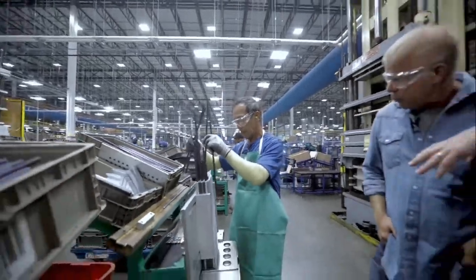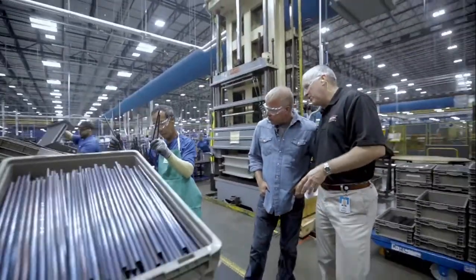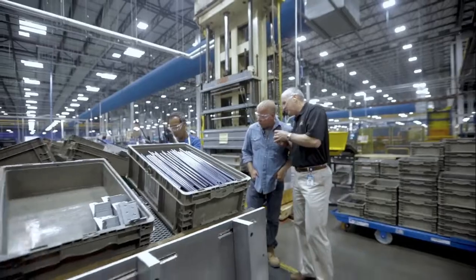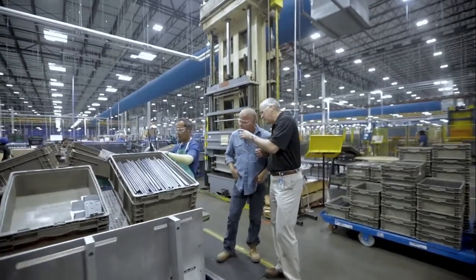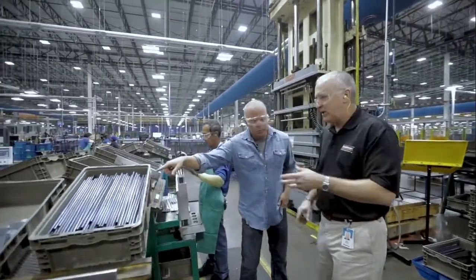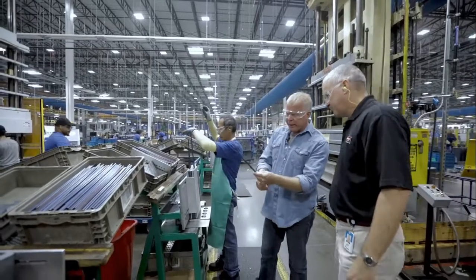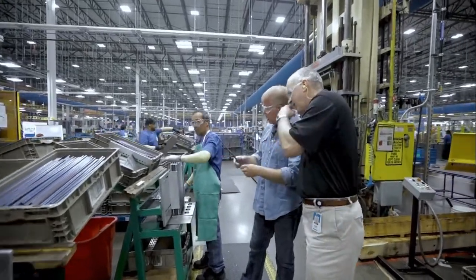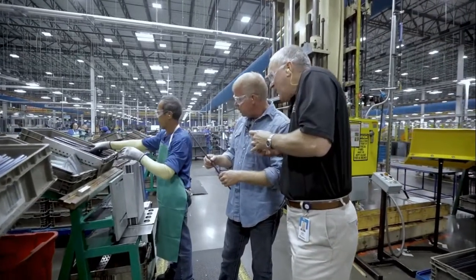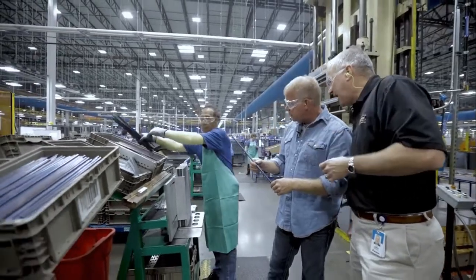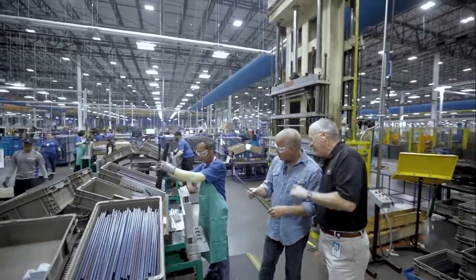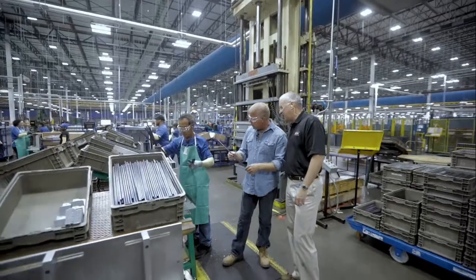Once he gets them all in, they go over to this next machine called an expander that expands the tubes to create a mechanical interference between the tubing and the fin. Can I touch one? Of course. This tube right here sits inside there, and it'll be expanded out so we get very good mechanical contact between the fin and the tube for good heat exchange.